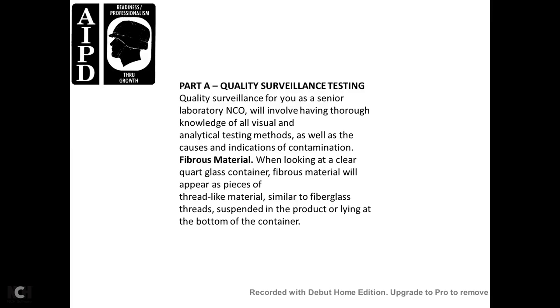Lesson 3: Supervise Quality Surveillance Testing. Part A: Quality Surveillance Testing. The senior laboratory NCO must have thorough knowledge of visual and analytical testing methods, as well as causes and indications of contamination. Fibrous material, when viewed in a clear quart glass container, will appear as thread-like material similar to fiberglass threads suspended in the product or lying at the bottom of the container.